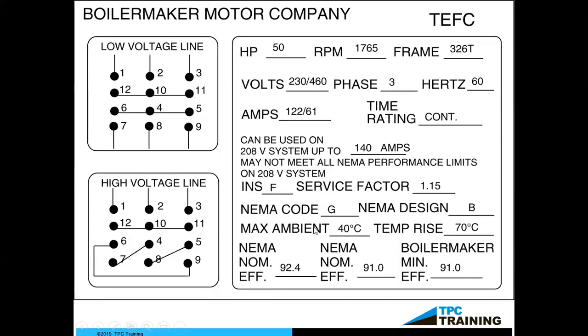They don't want us to install it in an ambient temperature above 40 degrees Celsius. And then it says temperature rise, 70 degrees Celsius. So what that temperature rise means is that's the allowable rise of the temperature of the windings inside over the ambient. So the stator windings are definitely going to produce heat because I have current flowing through them, and when that heat is produced, they don't ever want us to go above 70 degrees Celsius compared to the ambient. And so understand that that's how hot it can get before the insulation is going to be damaged.